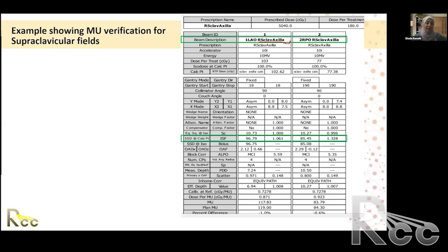So this is SSD at the calculation point. Remember, the calculation point is not necessarily at the isocenter. So you need to know the SSD at that calculation point. And then we have the off-axis ratio here. And what I want to show you is that the effective depth, you will use the effective depth for the PDD, but you will use the physical depth for the inverse square correction. And with all this complex information, we are within 1%.